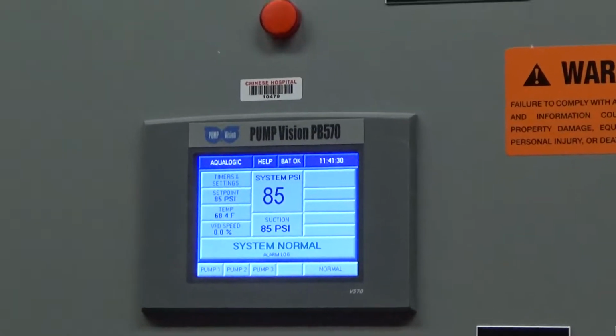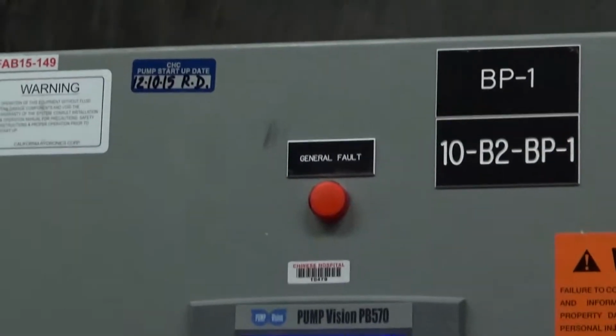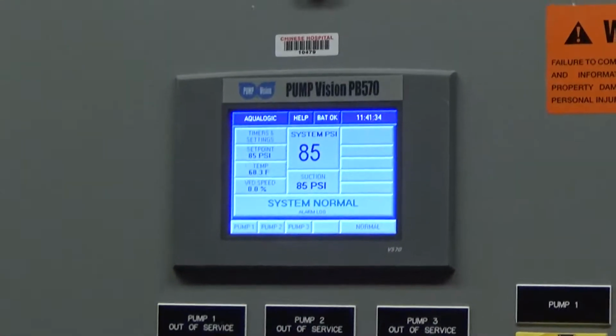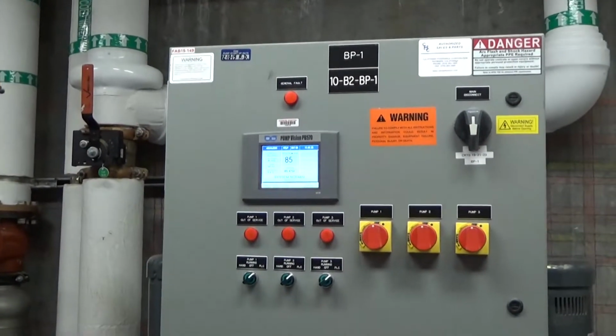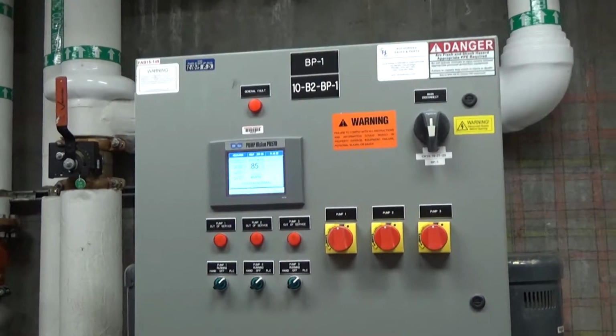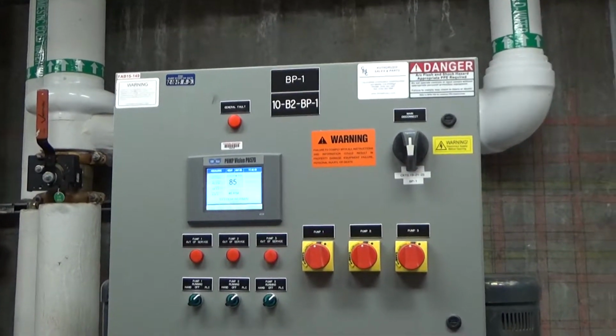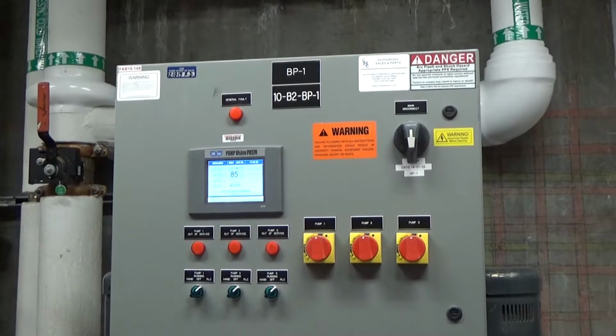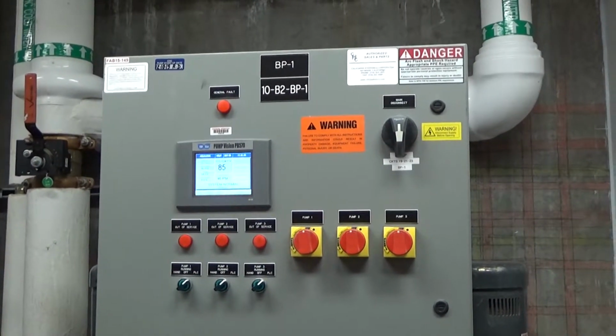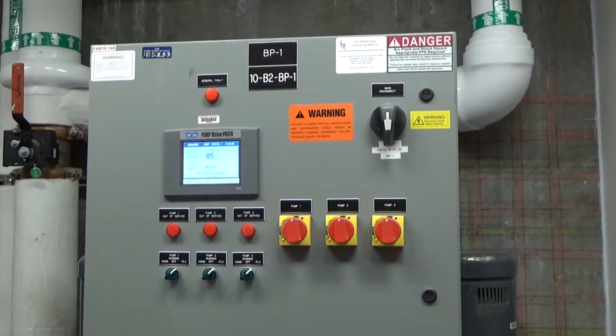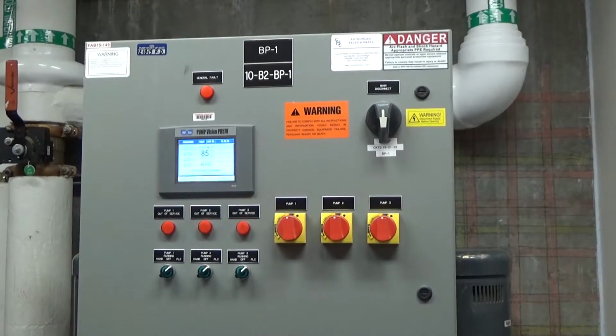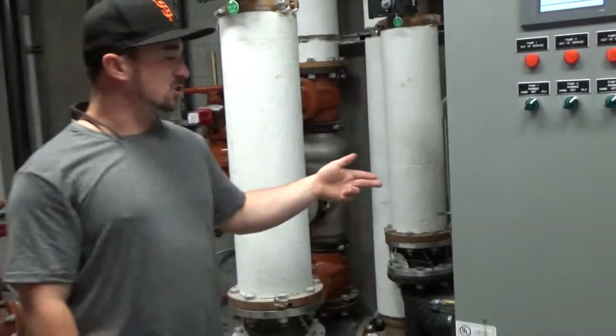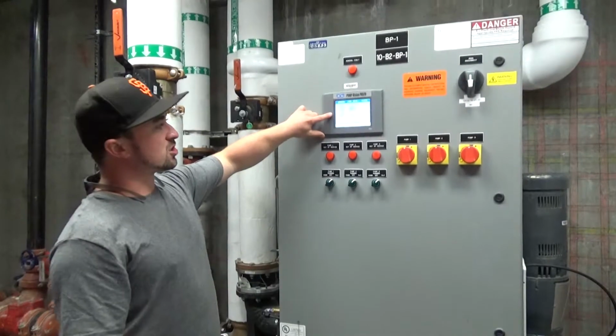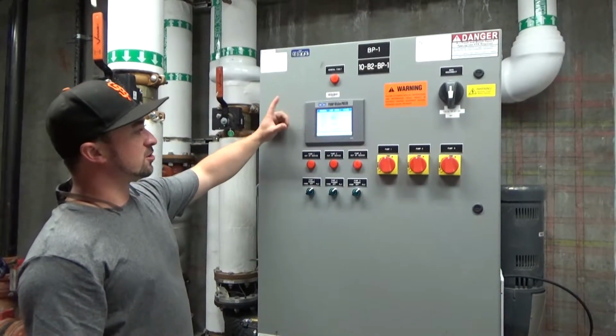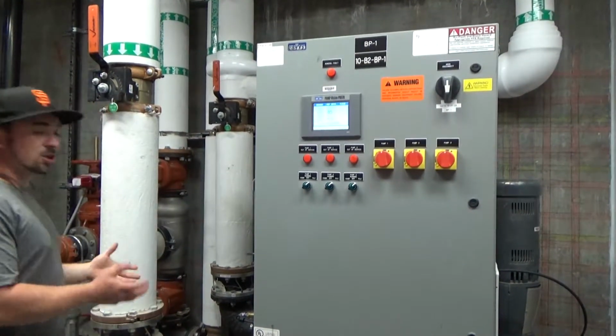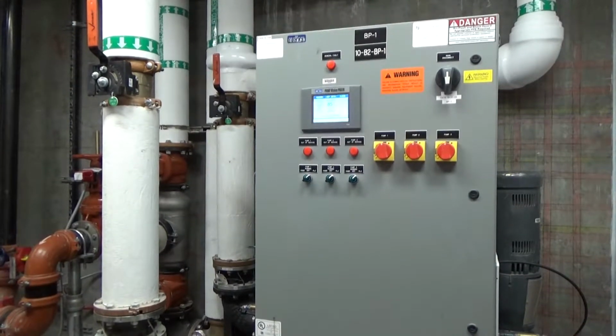This booster has a parameter so that if the water temperature in this booster goes over 100 degrees, everything shuts down. The purpose is, say this thing was just running and for some reason it was deadheading, and the water inside the loop just started heating up due to friction. There's no flow, but we're still pumping, and it's just getting hotter and hotter. To protect the seals on those pumps, this booster is going to start shutting off at 100 degrees, and it'll start alerting people, hey, something needs to happen. We need to take a look at this.